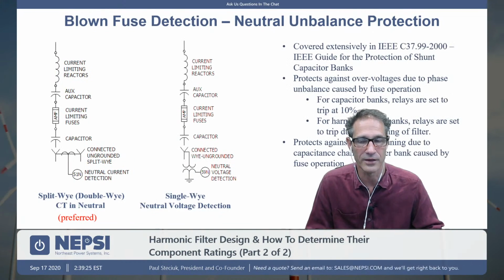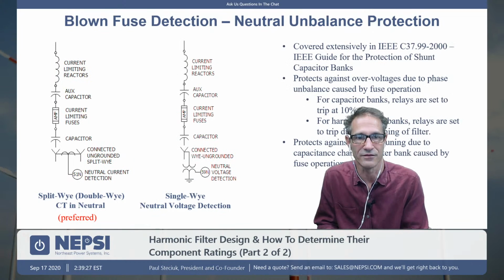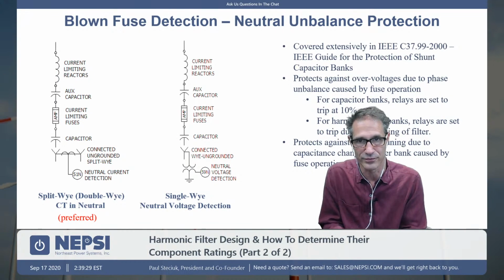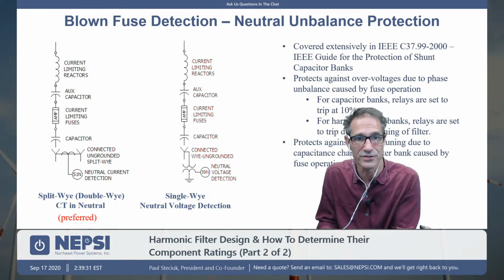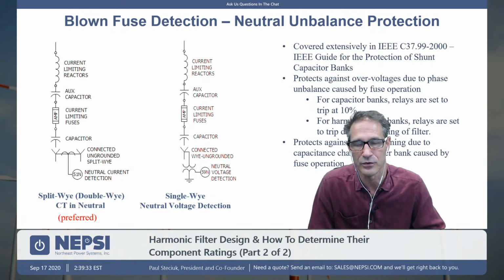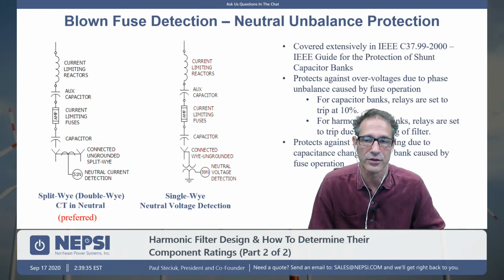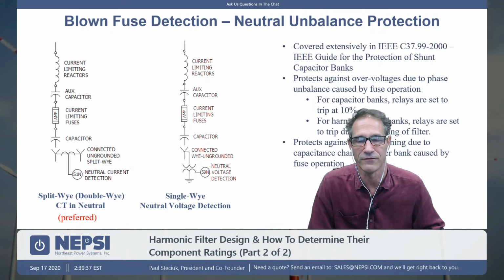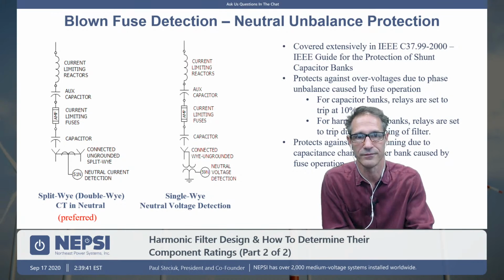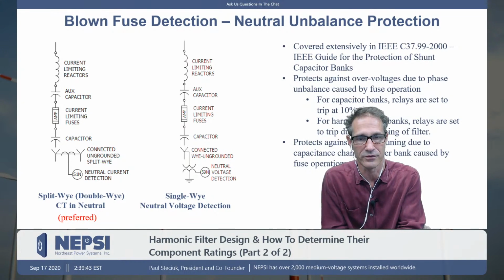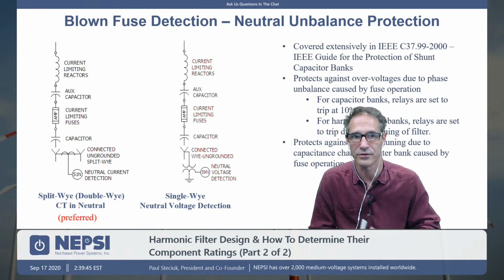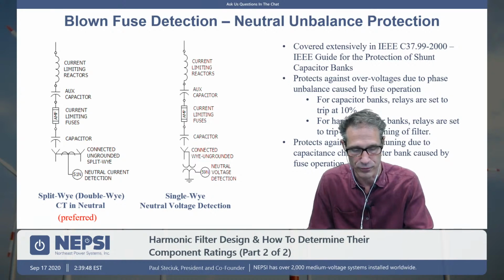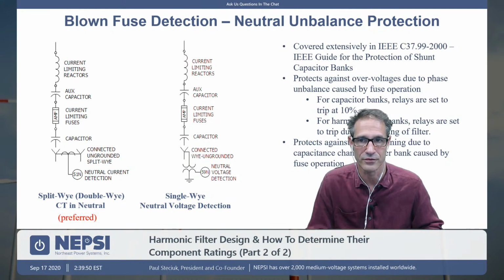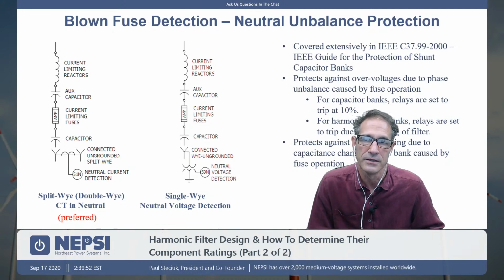If you take a capacitor offline, you potentially have to take the filter offline, which can also potentially require that the plant be shut down. So always think about what are the ramifications for a filter failure. And the filter failure could be as simple as I operated the fuse because of a failed section within the capacitor, right? So it's important to try to design filters so that they're very reliable.